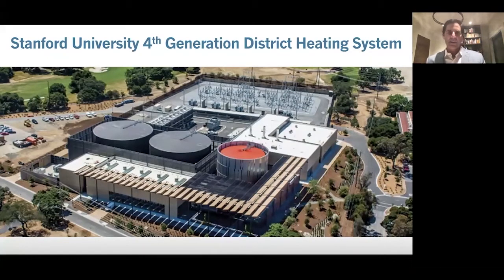Stanford then bought or purchased 120 megawatts of solar, put 10 megawatts on rooftops, and then built two power plants, a 15 and a 60 megawatt solar power plant, to offset the electricity. The second power plant is almost done, and it'll be done in 2021. When that's done, the campus will be 100% renewable, not only for electricity, but also heating and cooling. It replaced the entire natural gas plant, and the system is very reliable. District heating can be done on lots of campuses and also in cities and high density areas, and it's very effective.